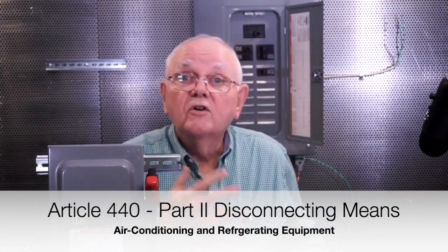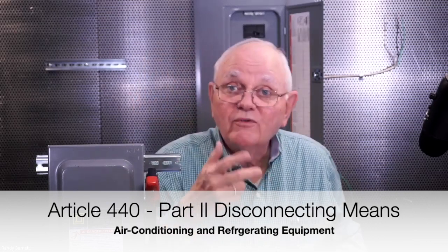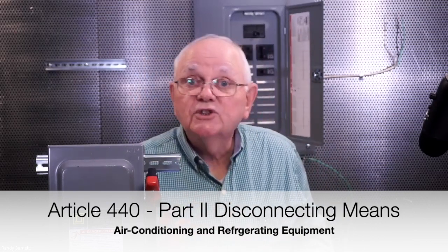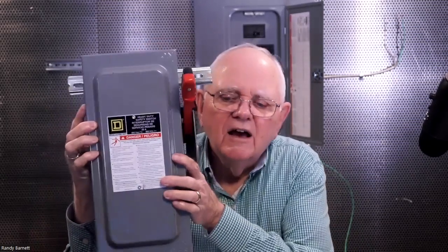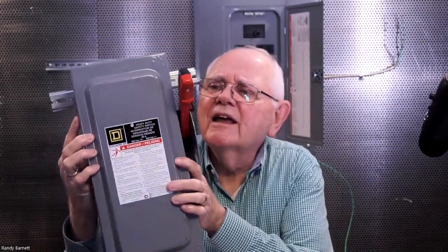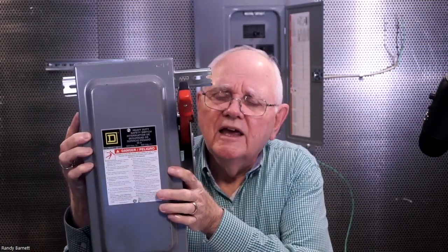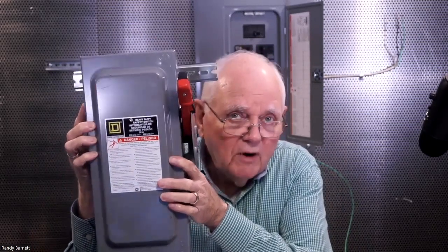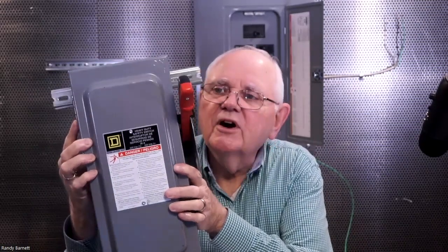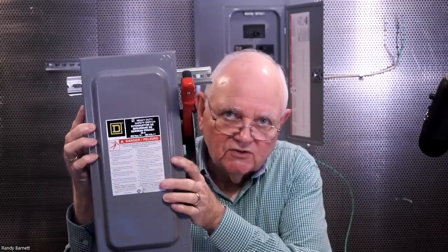So here we are, Article 440, air conditioning and refrigerating equipment. Part 2 is on the disconnecting means. The bottom line is that I want to make sure that this one disconnect, when I shut the power off to that air conditioning and refrigerating equipment, de-energizes not only the motor compressor itself, but also the control circuits. And always read your rules, right? You're going to find exceptions and different ways of doing things.